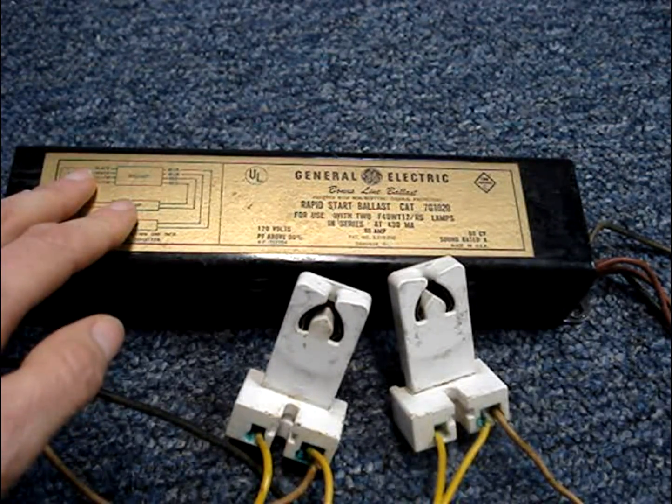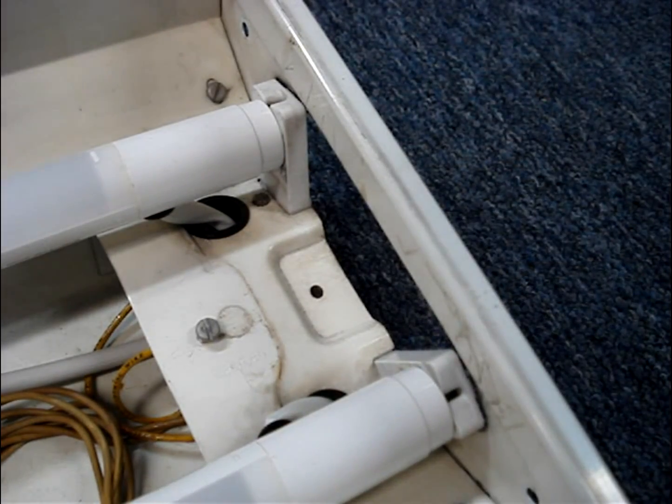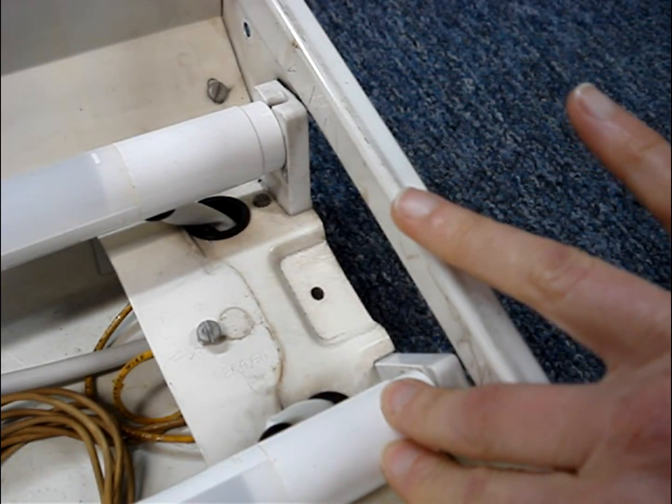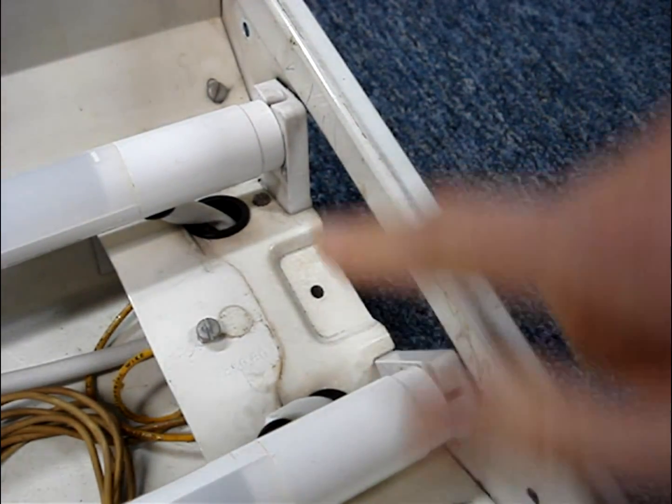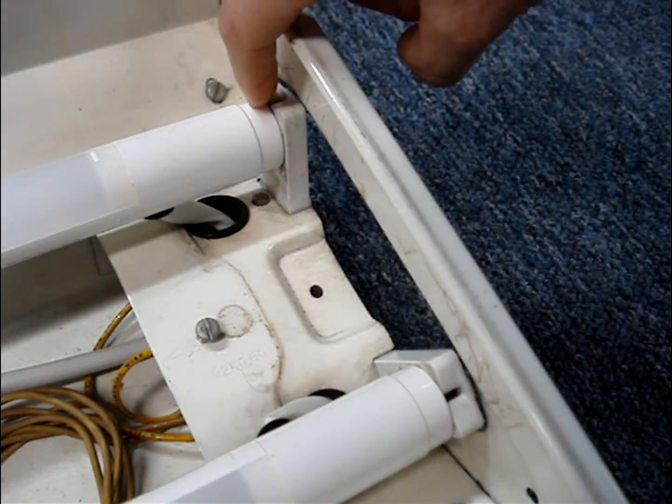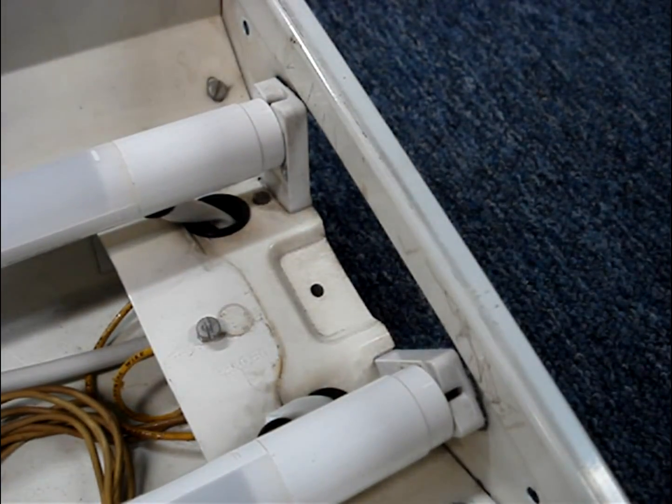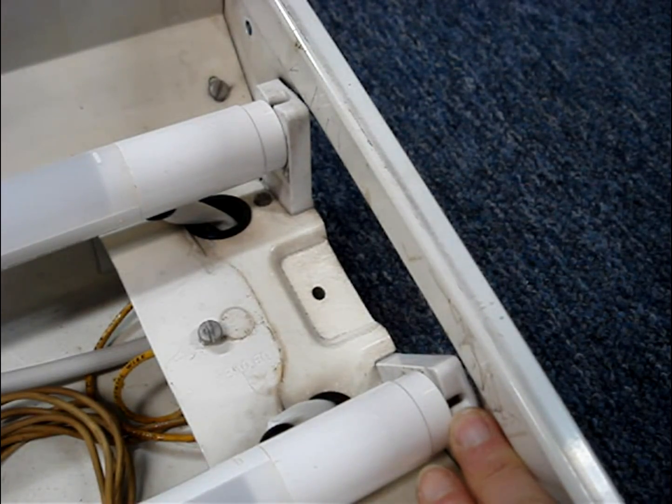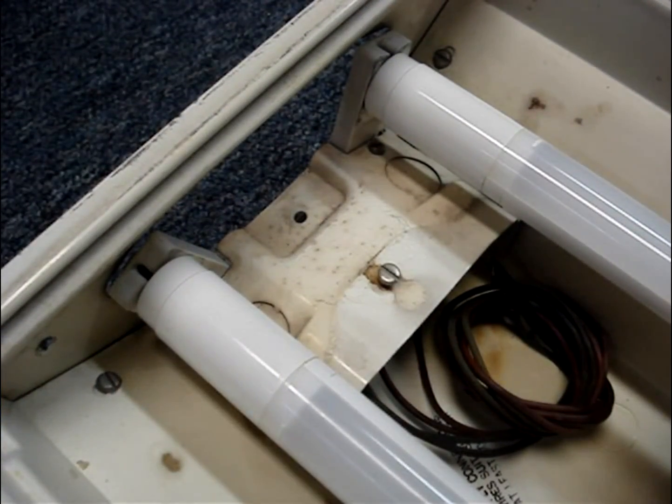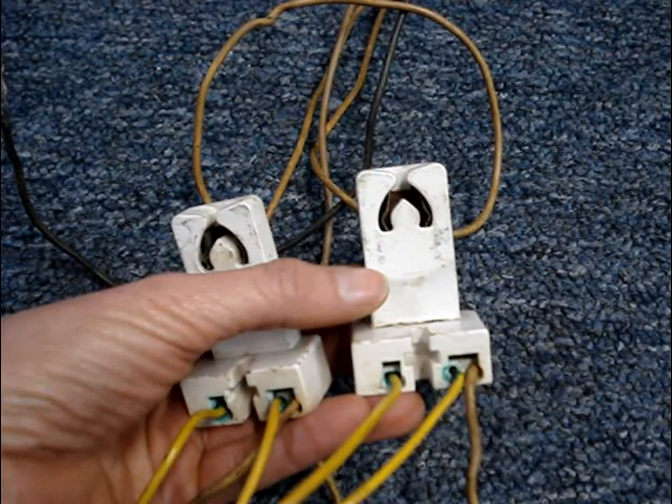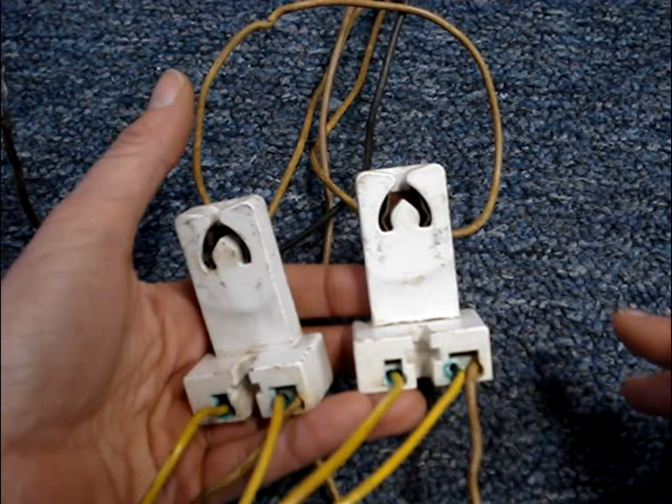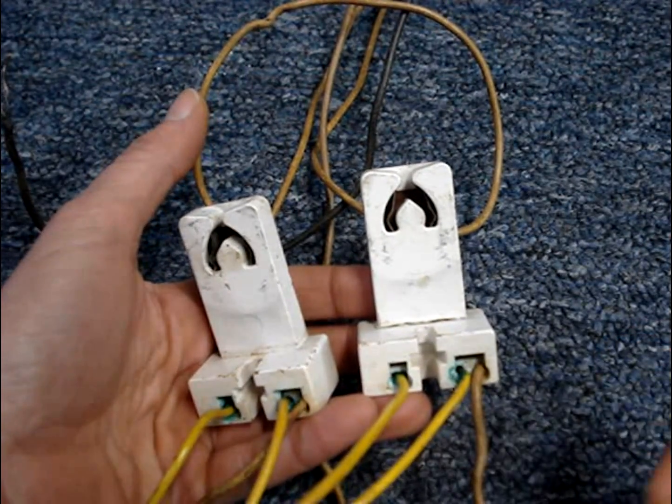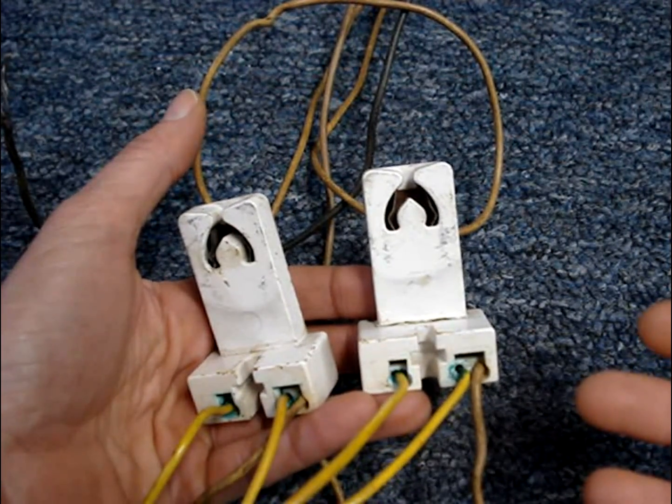The ballast gets removed. Depending upon the brand that you buy, they may apply 120 volts to the sockets on just one end of the tubes. Some brands you'll wire the tombstones on one end of the tubes with the hot and the other end with the neutral. You'll probably have to figure out whether your tombstones are the shunted or non-shunted kind and you may have to replace them.